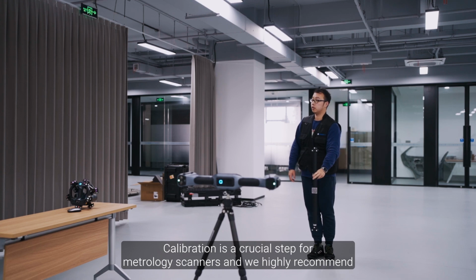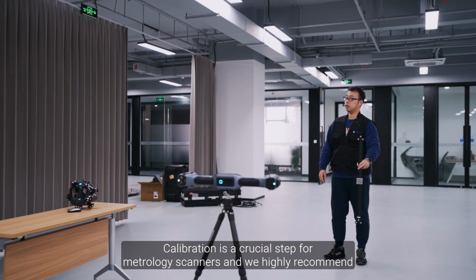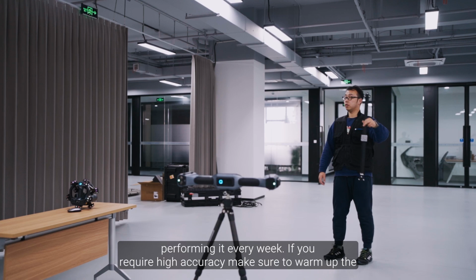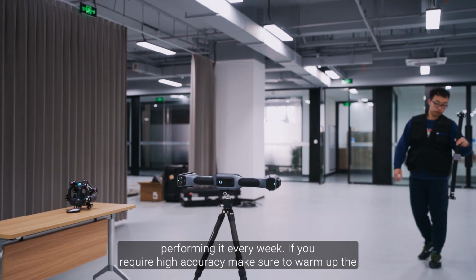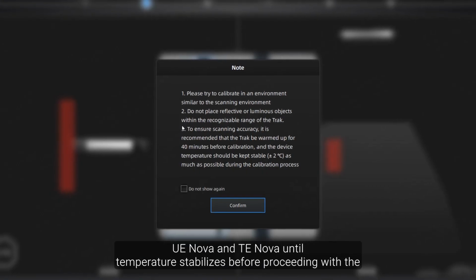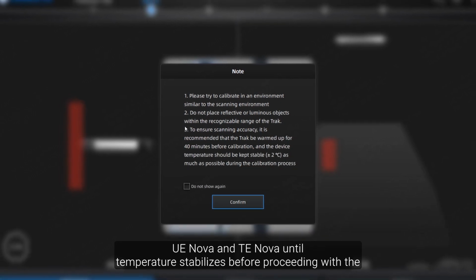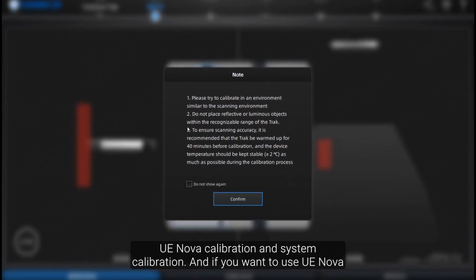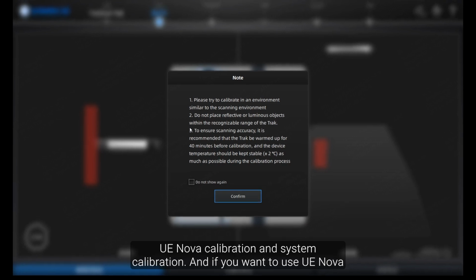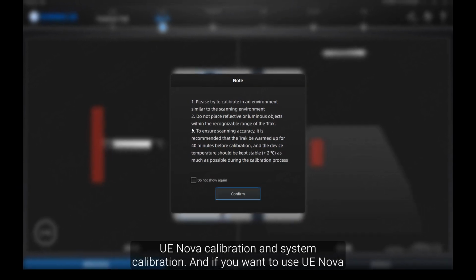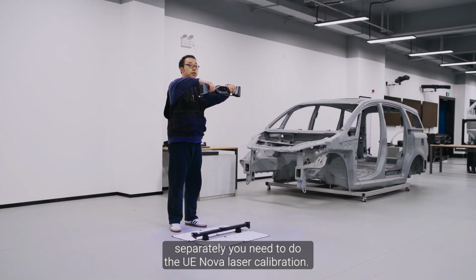Calibration is a crucial step for metrology scanners, and we highly recommend performing it every week. If you require high accuracy, make sure to warm up the UE Nova and TE Nova until temperature stabilizes before proceeding with the UE Nova calibration and system calibration. And if you want to use UE Nova separately, you need to do the UE Nova laser calibration.